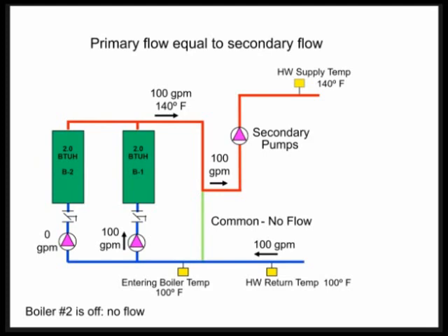Boiler number two is off. Boiler number one is on, and it's running wide open at 2 million BTUs. Is there a better way to do this? Remember the efficiency curve that we showed you, that boilers operating at 50% are more efficient than boilers operating at 100% fire in this condensing type product?